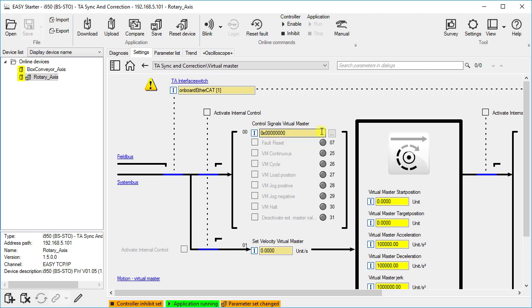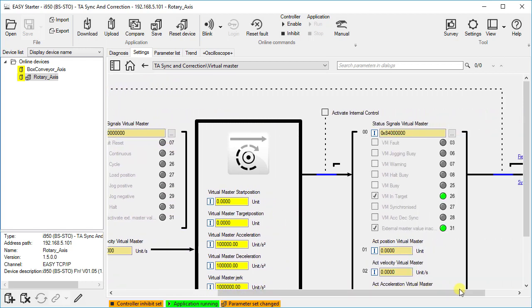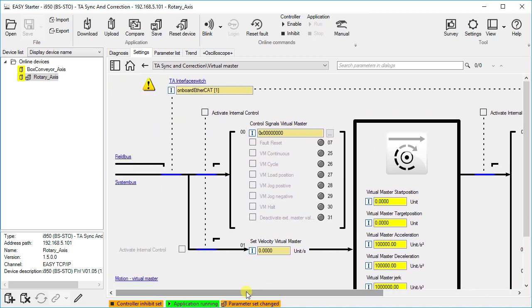For example, the fault reset is used to reset any fault in virtual master; for this purpose the status bit VM fault should be observed. VM continuous triggers the continuous driving operation of the virtual master. VM cycle triggers the virtual master for one complete cycle from its starting position to the target position. VM load position loads the starting position of the virtual master. VM jog pos and VM jog neg are used for manual jog in positive and negative direction. There are separate parameters for this in the motion control, which you will find in the commissioning step motion virtual master.